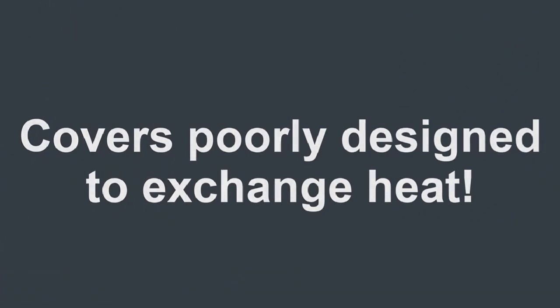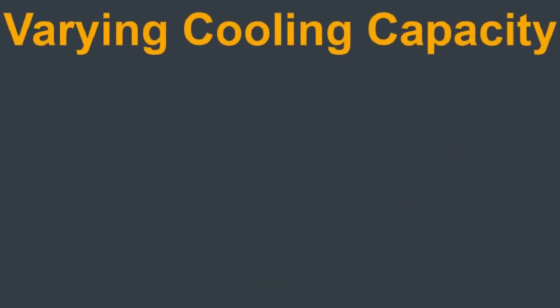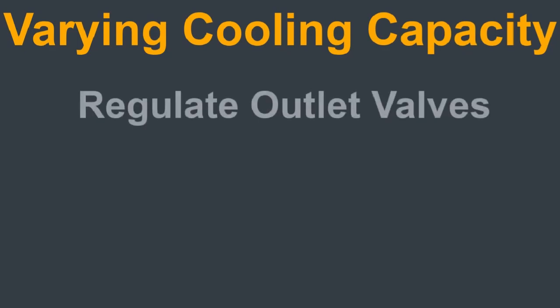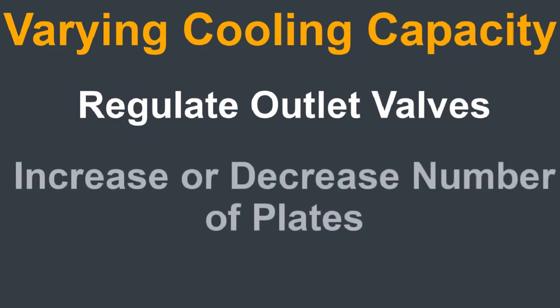There are several ways to vary the cooling capacity of a heat exchanger. One way is to regulate the outlet valves so that the flow is increased or decreased. This method is useful because no dismantling of the heat exchanger occurs. Another way is to increase or decrease the number of plates in the plate stack. Increasing the number of plates in the plate stack gives a corresponding increase in cooling capacity. Decreasing the number of plates in the plate stack gives a corresponding decrease in cooling capacity. In short, more plates equals more cooling, and less plates equals less cooling.